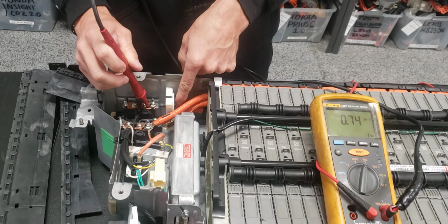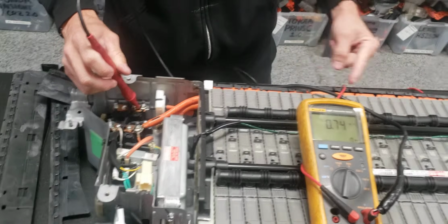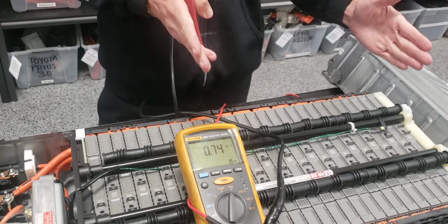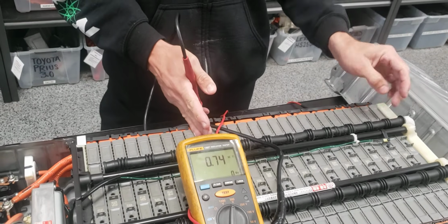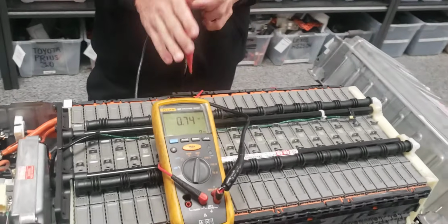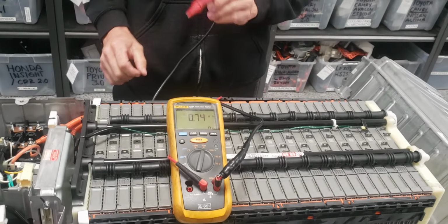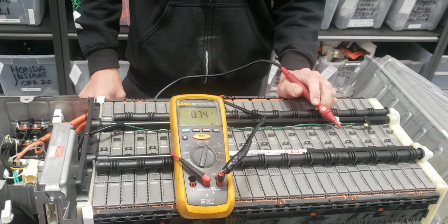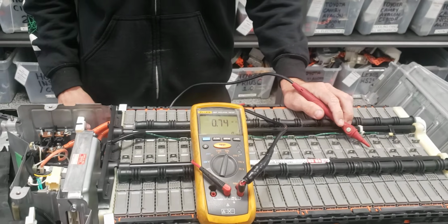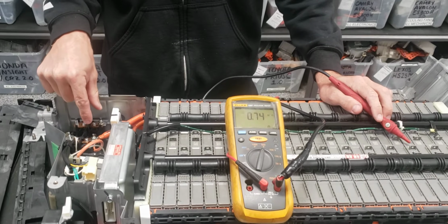If you guys remember, the heavy gauge wire on the bottom runs all the way to the end, so our problem is over here on this side. You can disconnect all the bus bars from one side or the other and touch and figure out exactly which cell has failed. But in the actual field, all you need to do is test here and you will know.